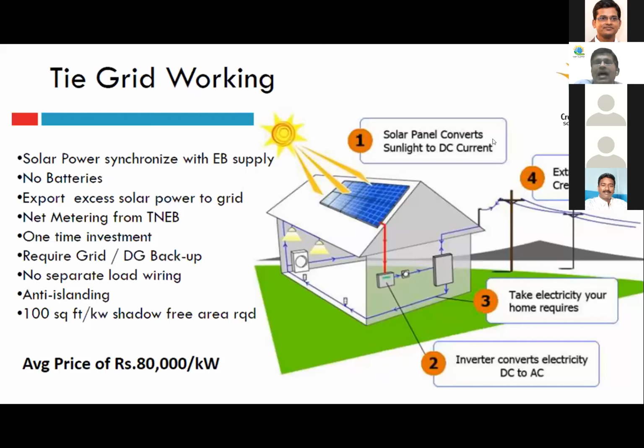Let's say during a power cut, my system will not work. That's the technology. That's called anti-islanding. And all the on-grid solar inverter manufacturers have to comply with this technology called anti-islanding, which means I'm not supposed to generate electricity when there's a power cut. One obvious reason is, suppose I start exporting during a power cut, let's say it's a Sunday and there's no load at my office, and I start exporting this power out. What happens? The maintenance people on the electricity side will have a shock hazard, which is very dangerous. So to avoid that, TNEB has strictly said you are not supposed to export any power outside your grid during power cuts, and your system should not work.